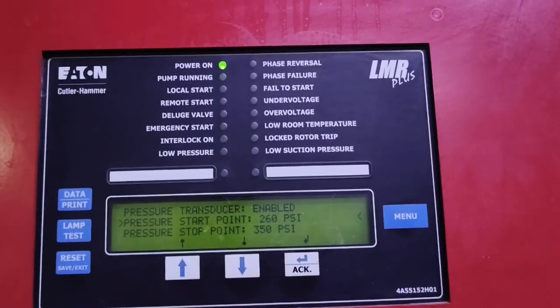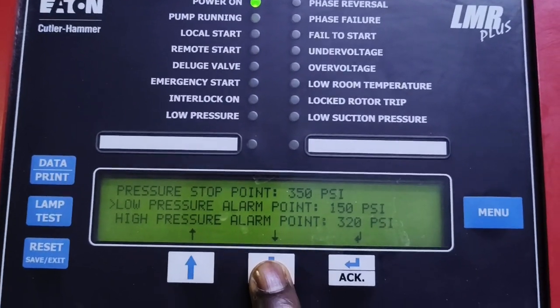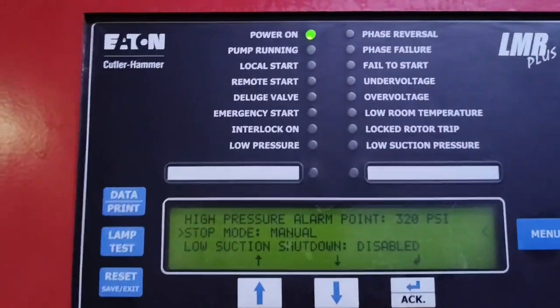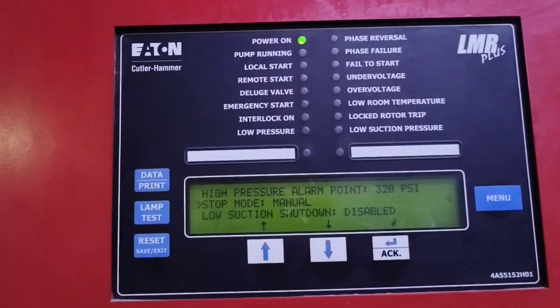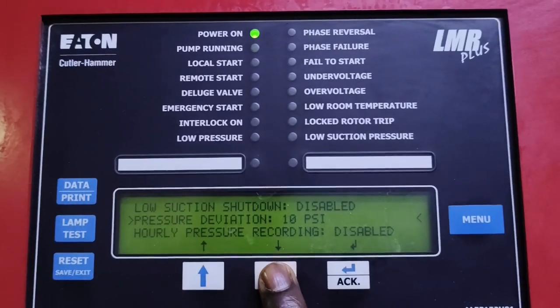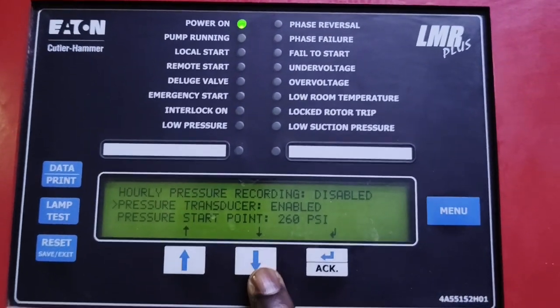The pressure start point has been set to 260. If you want to change it, because the password is disabled you can just click and use the up and down buttons to adjust it, then press enter. The pressure stop point is 350. The low pressure alarm point is 150 psi. High pressure alarm is 320. The stop mode is manual, so even if it reaches the stop point it will not stop automatically — it has to be manually shut down. Low suction shutdown is disabled and pressure deviation is 10 psi. Hourly pressure recording is disabled.